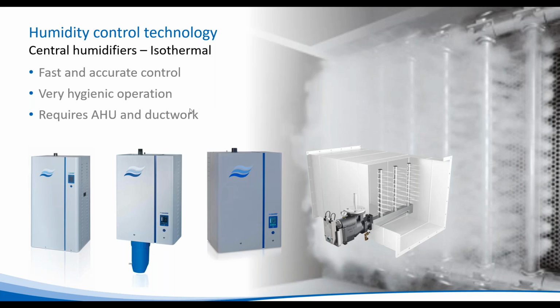Now, there are also different types. This is a resistive heater with inbuilt scale management, and that will typically be used where closer control is required or where we've got questionable water quality, because you can use water treatment on these systems. So it's very common in, let's say, a museum application in London, where we've got hard water, to use reverse osmosis treated water and a resistance heater humidifier. And this will closely control the relative humidity, typically to plus or minus 5% RH. And then there are other options.